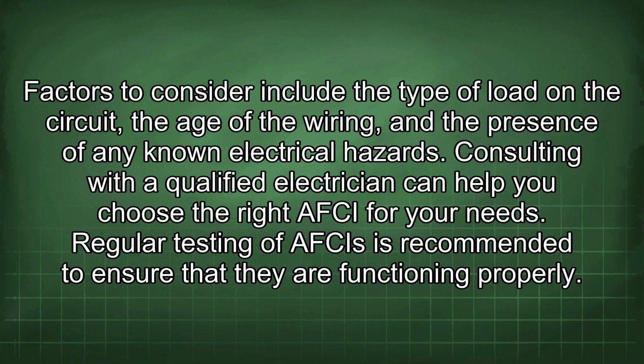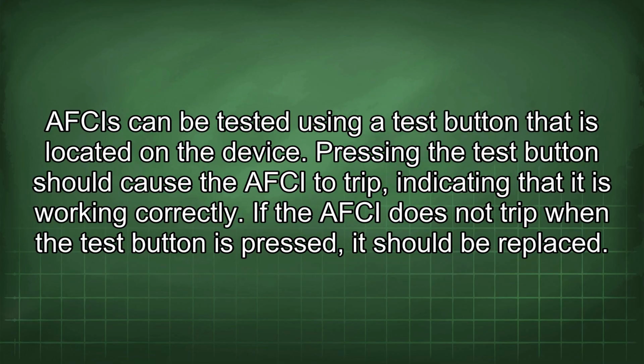Regular testing of AFCIs is recommended to ensure that they are functioning properly. AFCIs can be tested using a test button that is located on the device. Pressing the test button should cause the AFCI to trip, indicating that it is working correctly. If the AFCI does not trip when the test button is pressed, it should be replaced.